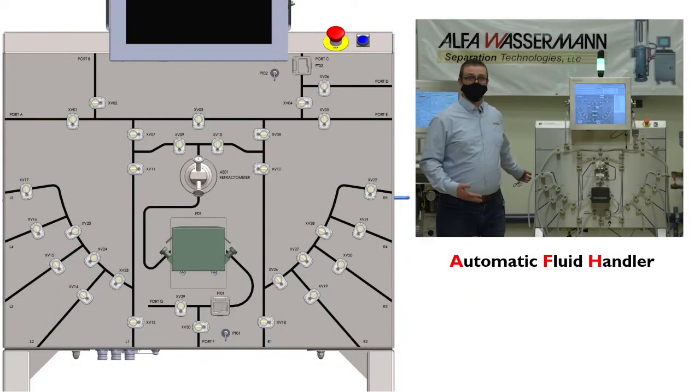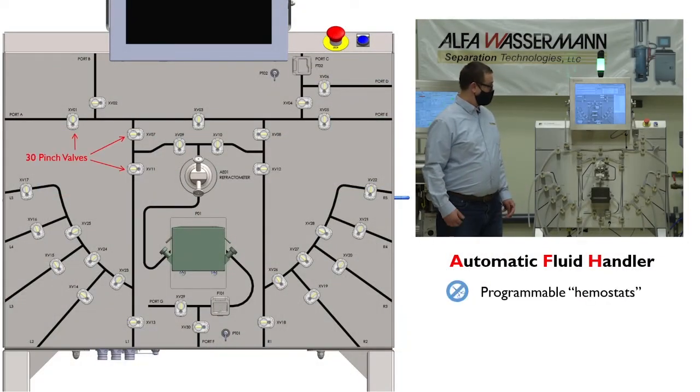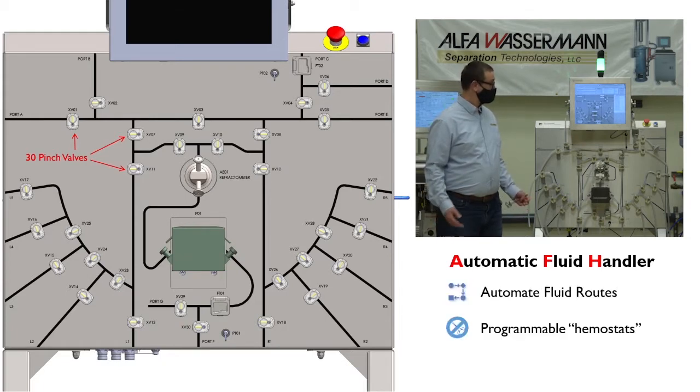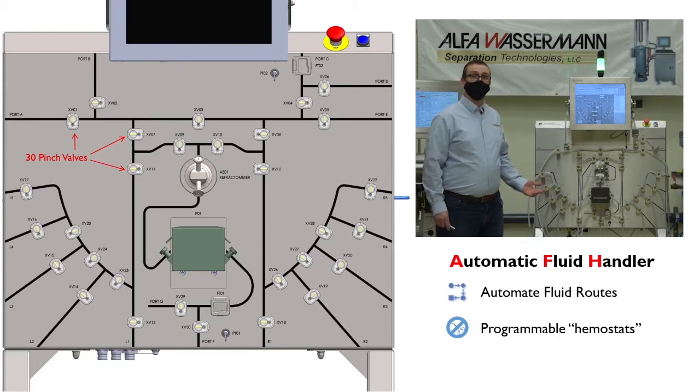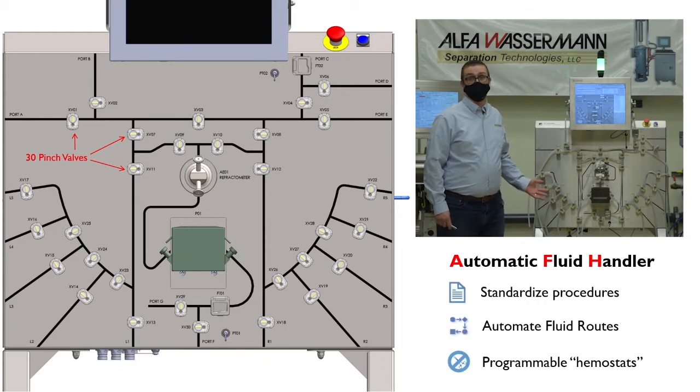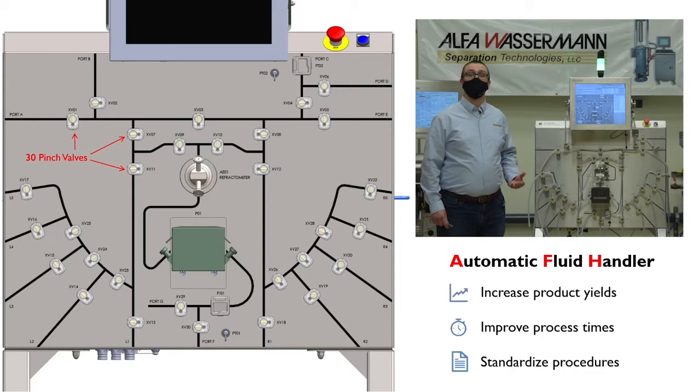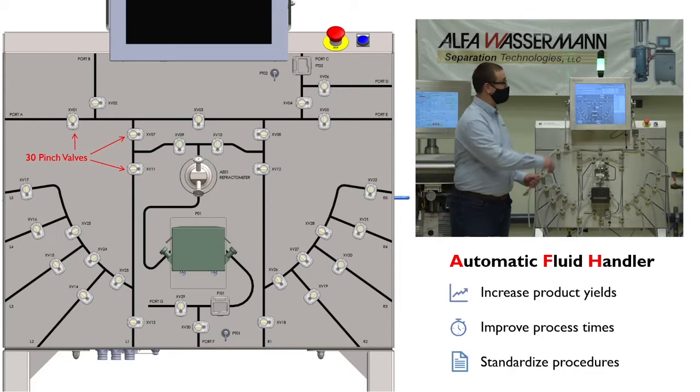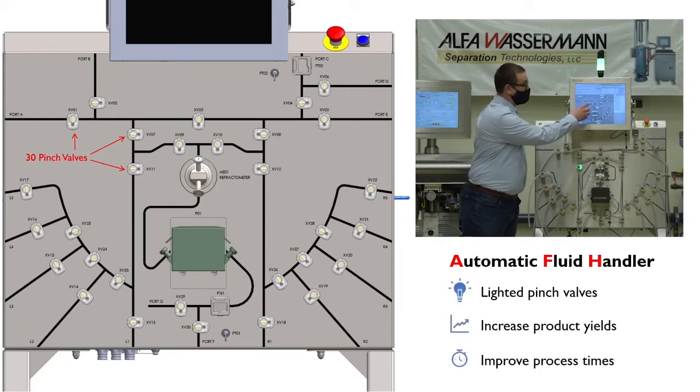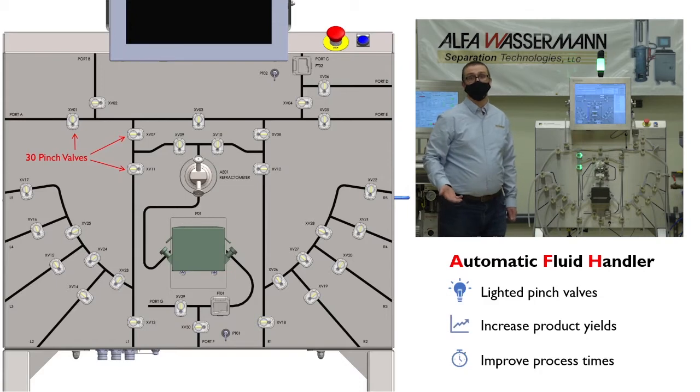We've replaced traditional hemostats with a series of 30 programmable pinch valves. Fluid paths can be automatically routed by opening and closing valves based on a defined method. This eliminates the need for an operator to determine and manually route fluids during critical process steps, which improves method performance and increases product yield. As these paths are open, the respective pinch valves are illuminated green, which makes it easier for an operator to monitor the entire process.